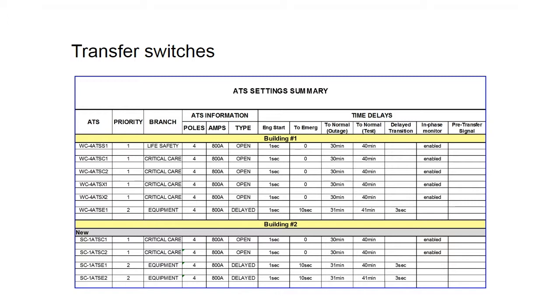The other loads you would add so that you maintain the system and ensure that there's capacity there to add these additional loads, particularly when you're looking at a multiple generator installation. I mentioned earlier that if you lost a generator, for instance, you would want to start then at the lower priorities and you begin to shed those to a point where you can ensure continuity of the system and maintain backup power for the most critical loads of the critical functions within your facility.